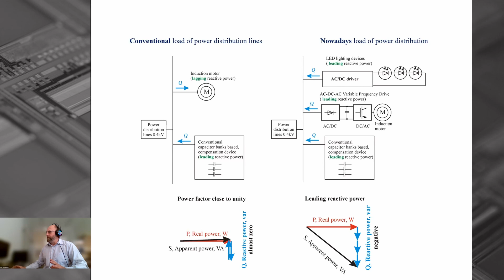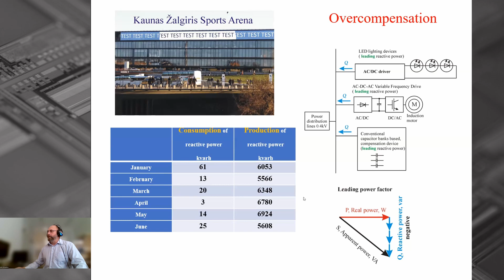We can see that situation from the data presented in this table, taken from the power distribution lines in Žalgiris Sport Arena in Kaunas. The production of reactive power is much bigger than the consumption. That means that the company operating this sport arena pays fines for the reactive power to the power supply company. How to solve this problem? We would like to present 3 ways of solving it. The first way, to bypass the variable frequency drive. The second way, by modifying the conventional variable frequency drive. And the third way, by replacing the conventional variable frequency drive with a novel matrix converter based variable frequency drive.